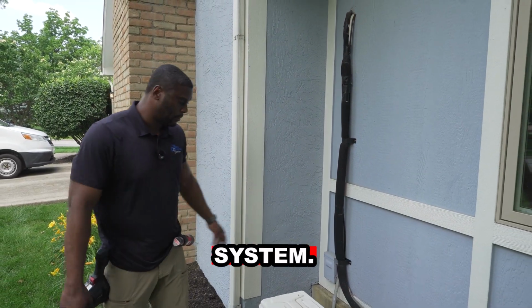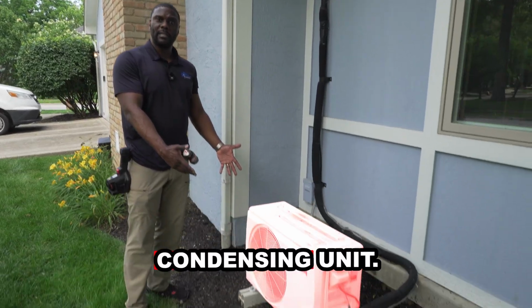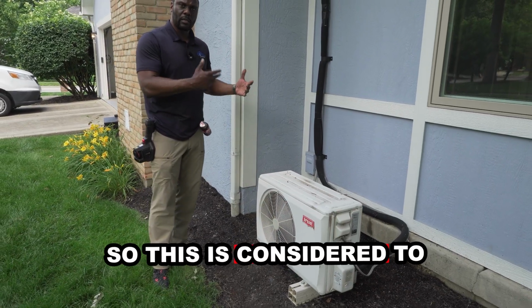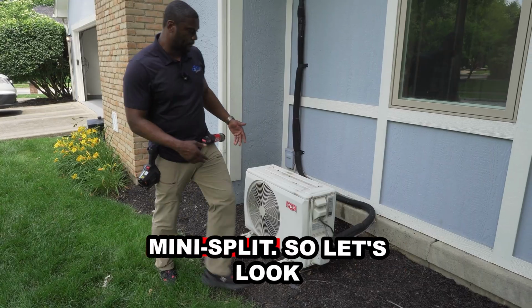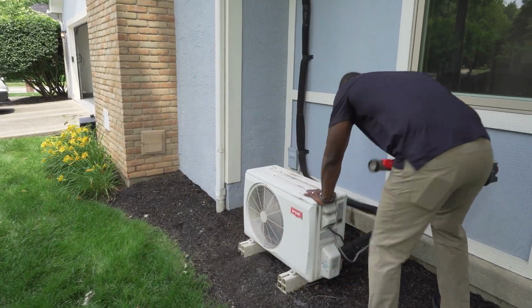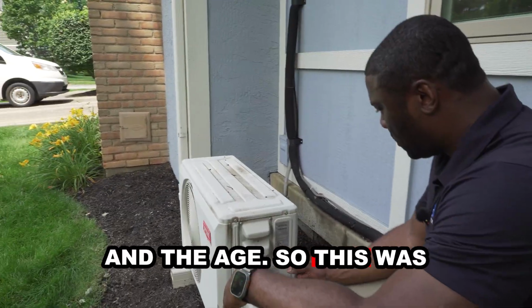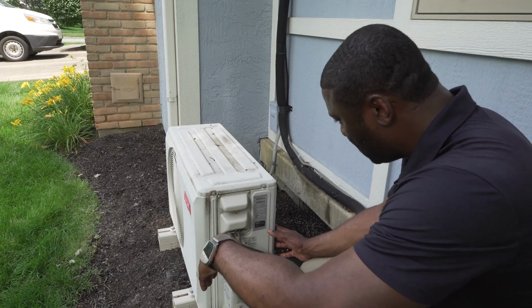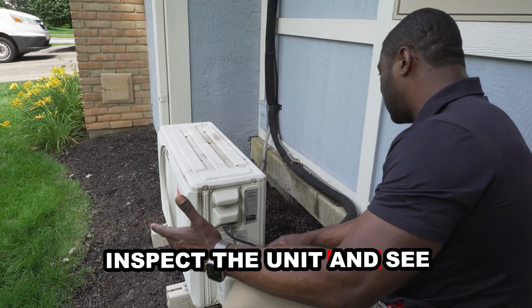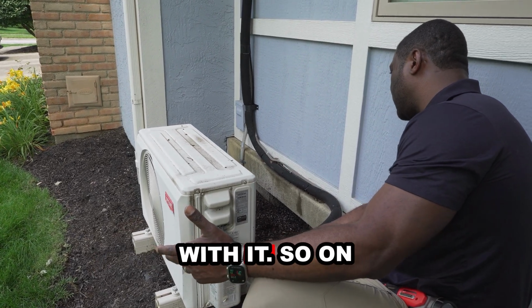It's a ductless system. This is your outside condensing unit. So this is considered to be a heat pump, but it's a mini split. So let's look at the sizing on it and the age. So this was built in 2016 and it's a 1-ton unit. And so let's just inspect the unit and see kind of what's going on with it.